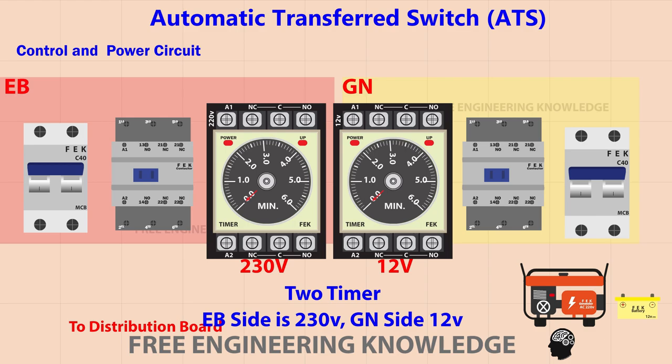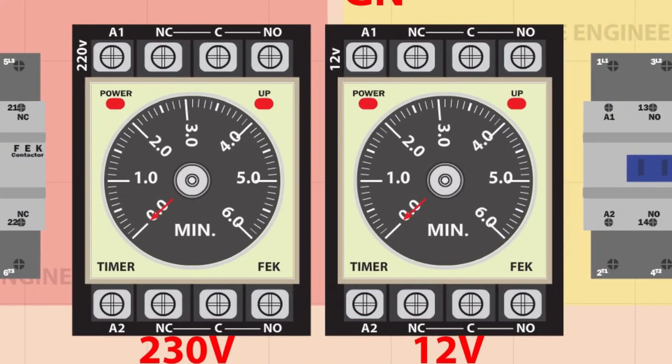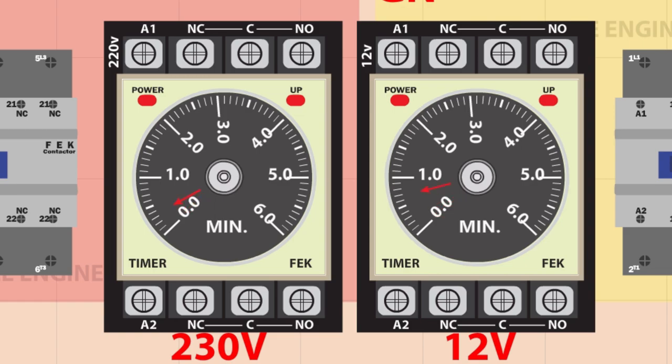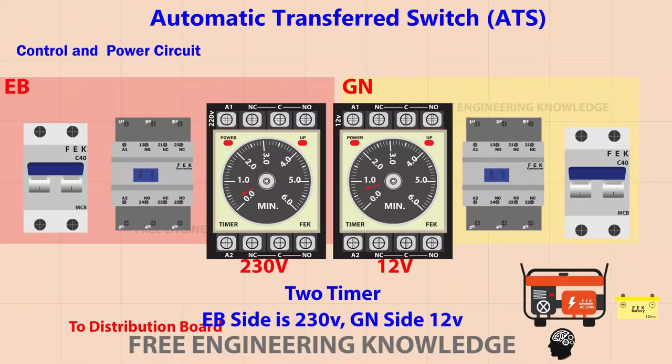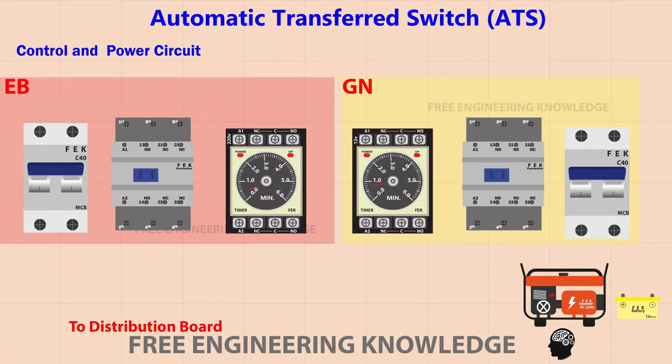Why should we use timers? Sometimes there is a power cut on the EB side and it comes back on suddenly, which can affect the electronic devices in our home. These two timers are used to avoid this. Specifically, the timer on the generator side should be set slightly longer than the timer on the EB side.